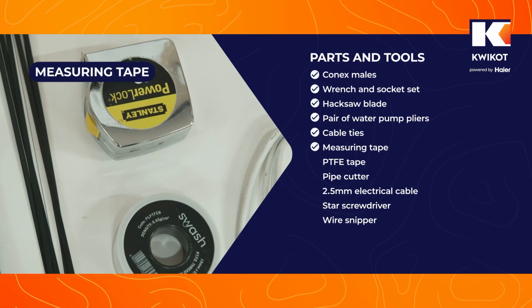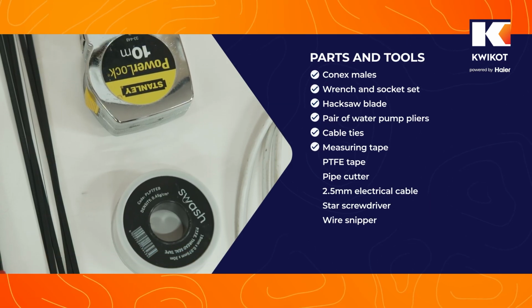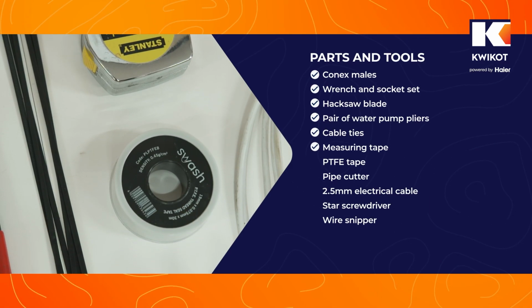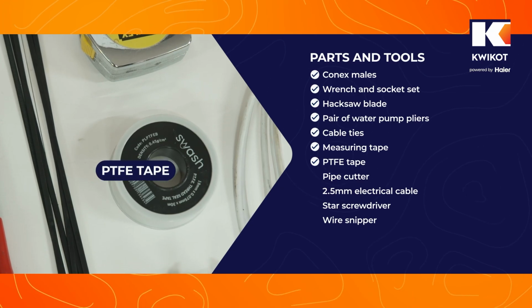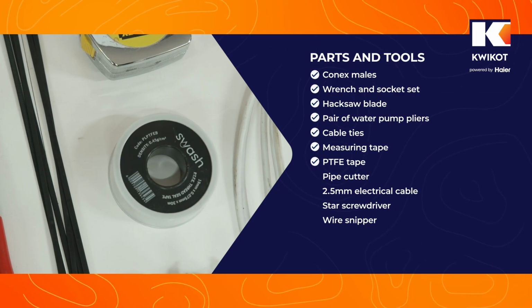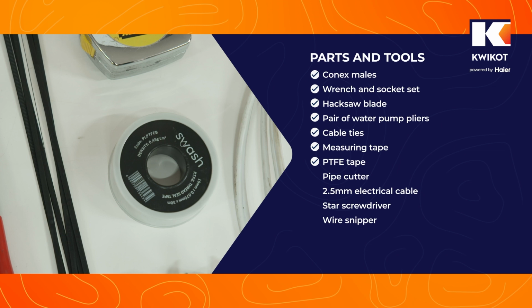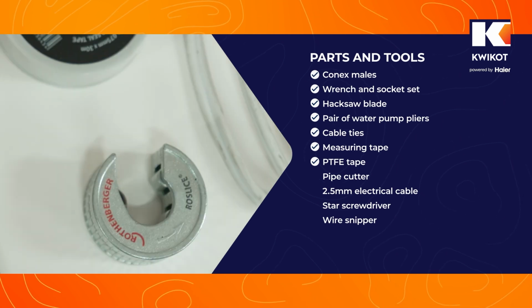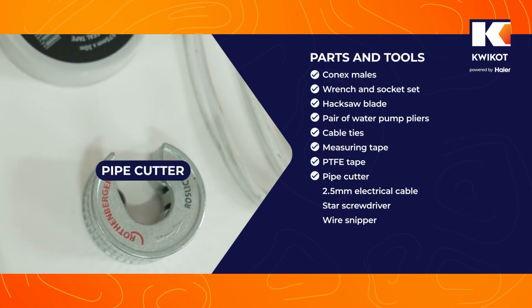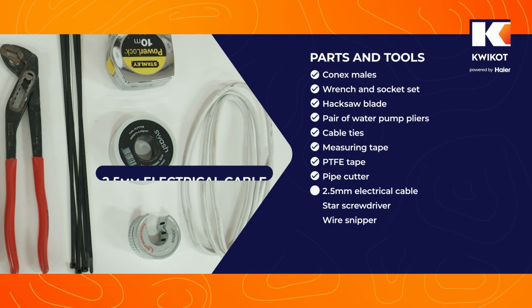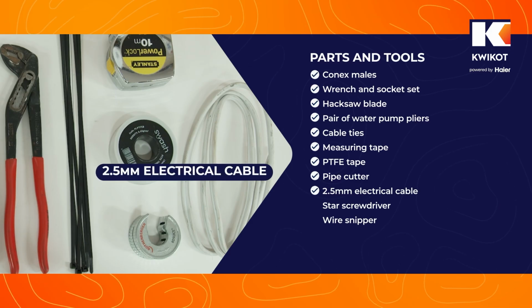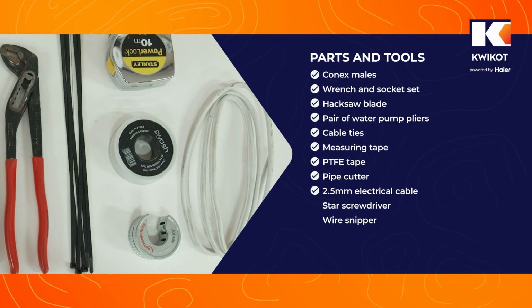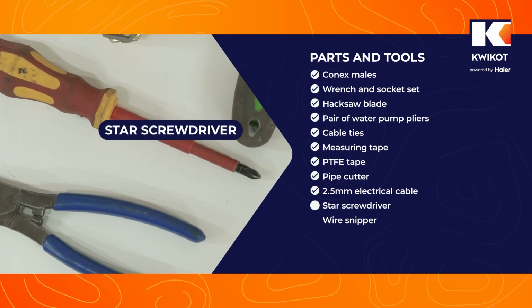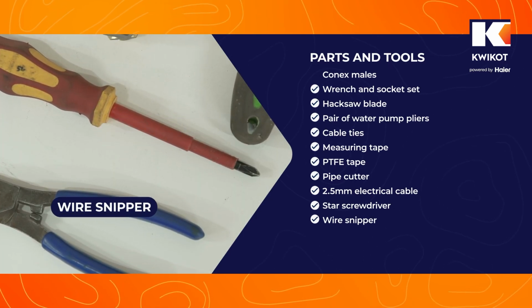Some measuring tape just to measure the lengths of the pipes that you will need to cut, and then we have some PTFE tape for sealing the pipe threads. Alternatively, you can also use hemp for this instead of PTFE tape. Then we will also need a pipe cutter to cut the copper piping, and some 2.5mm electrical cable, which will be needed to supply power to the heat pump. And lastly, we will also need a star screwdriver and a wire snipper.